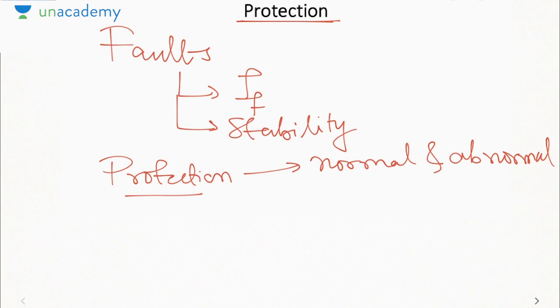Okay, let me give another example. In the case of machines, we study the magnetizing inrush current. We studied that it is very high compared to the full load current, but it persists for a shorter duration. Similarly, fault current is very high. Now, the protection system must be able to distinguish between these two currents because inrush current is not a faulty current, it is a normally occurring current. It will occur whenever the transformer is switched on. There is no means by which we can avoid magnetizing inrush current. So, any protection system must be designed in such a way that it does not operate for inrush current, but it must operate in case of a fault current.